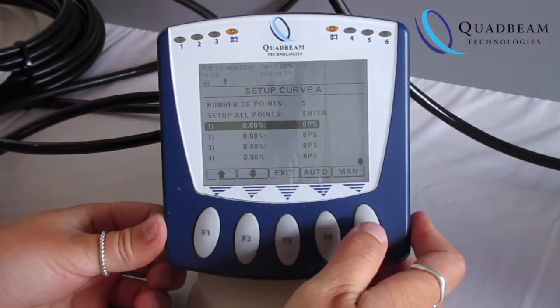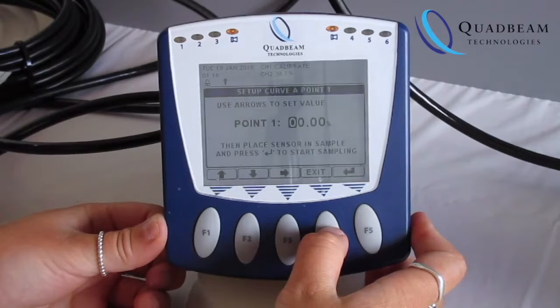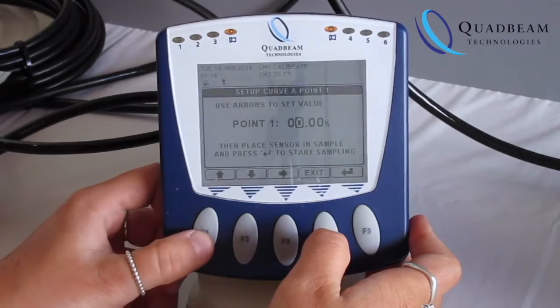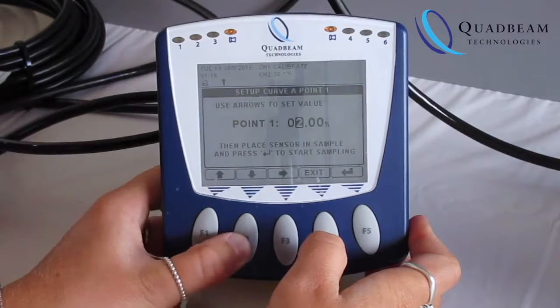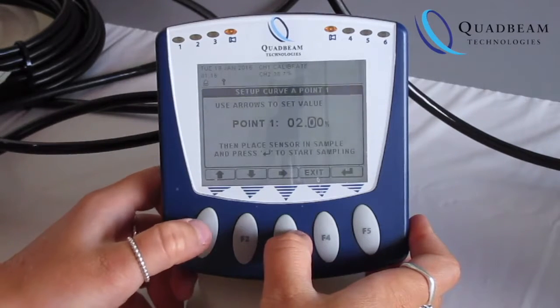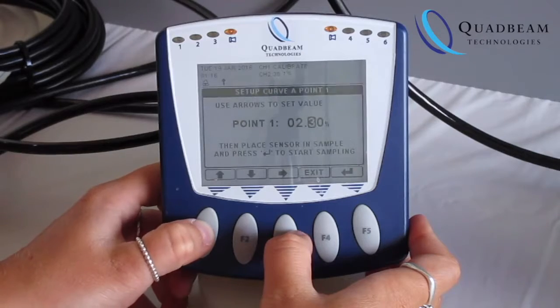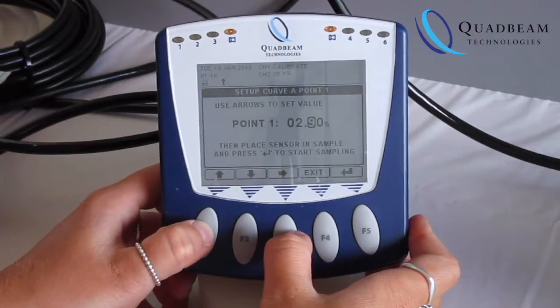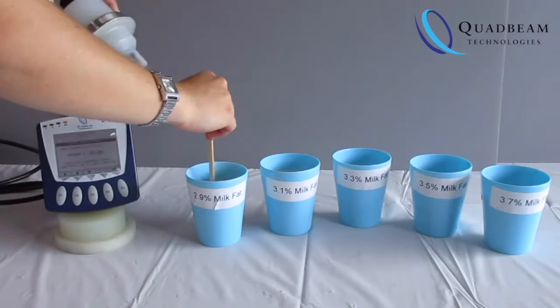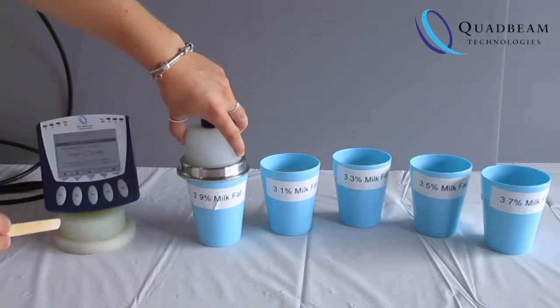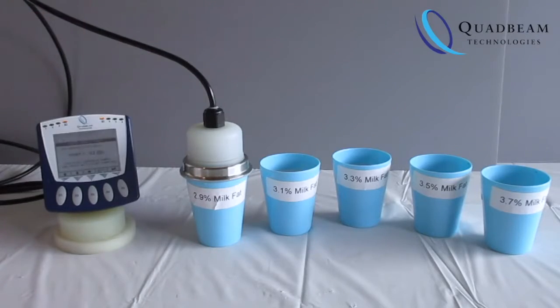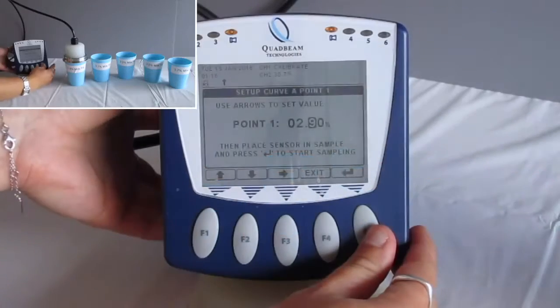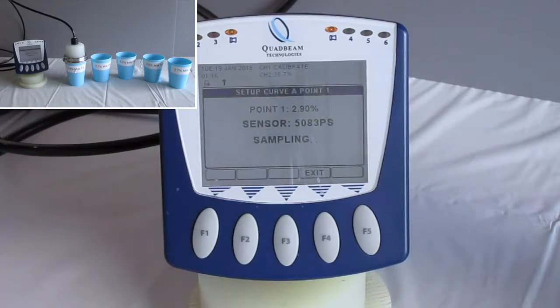Move to point 1, press auto, then input the concentration of the first sample. In this case it's 2.9%. Our target value is 3.3%, so we've picked 2 points above and 2 below the 3.3. Stir the sample, place the sensor as centrally as you can, and push enter. You'll see that the sensor is detecting the probe signals, and the system is applying that to the 2.9%.